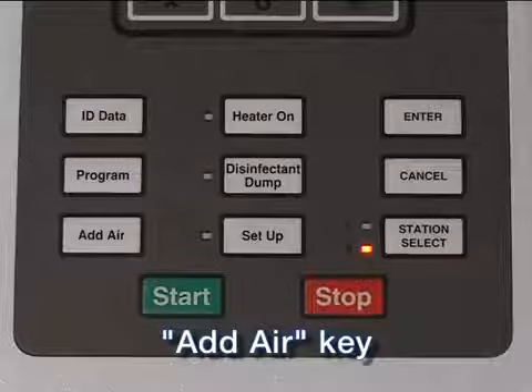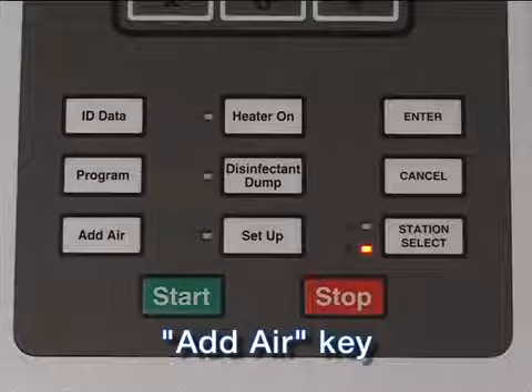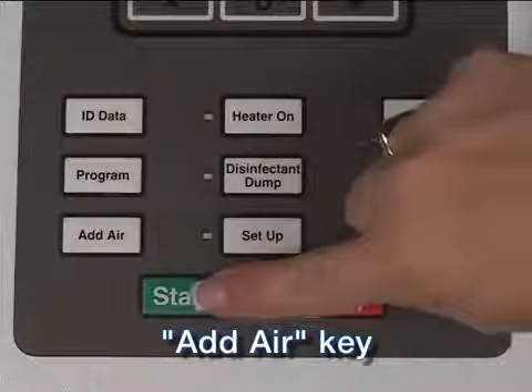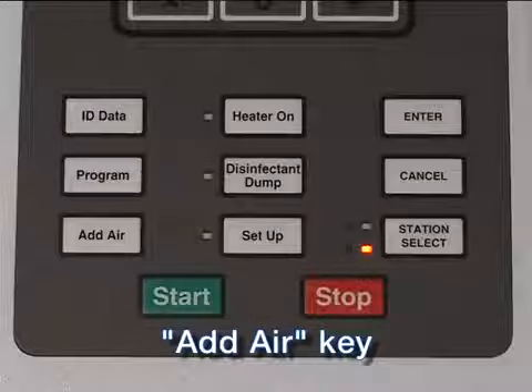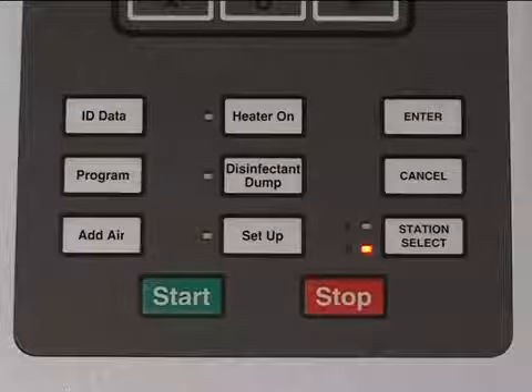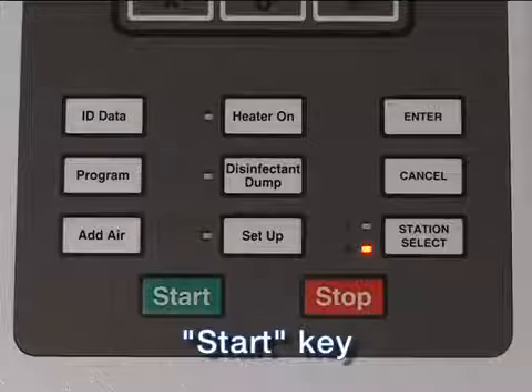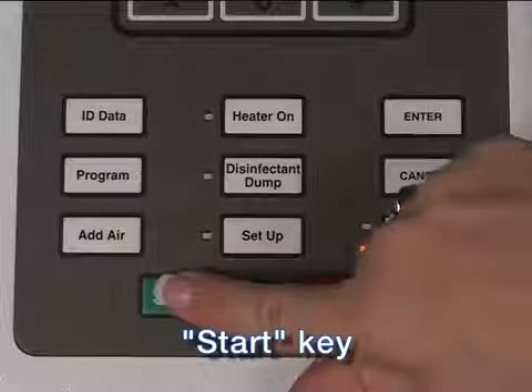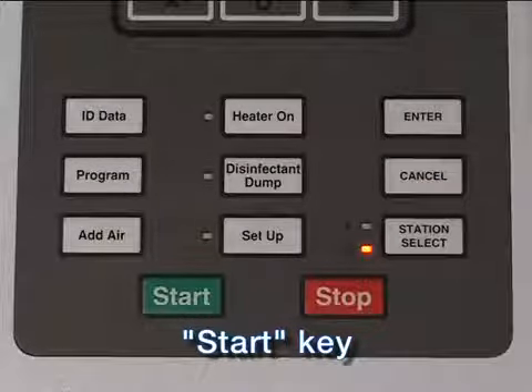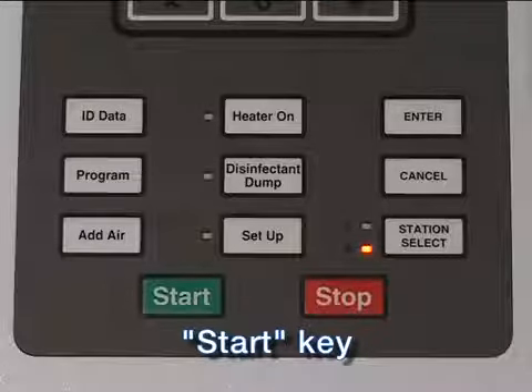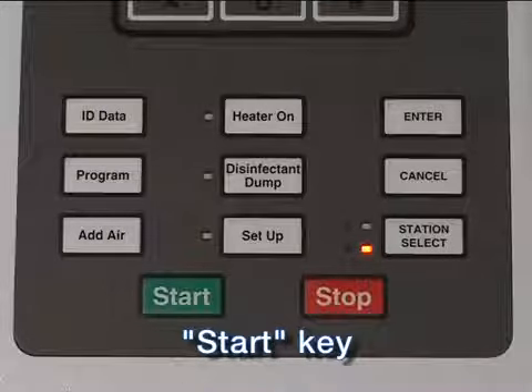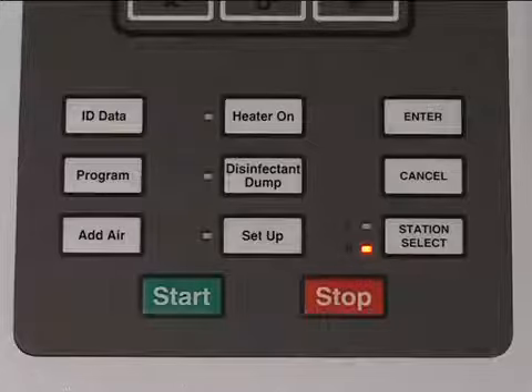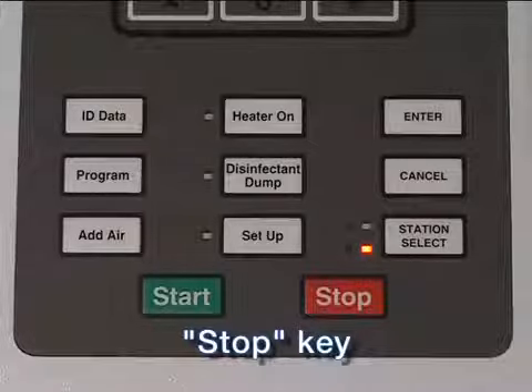Add Air key. Press this key, then the Start key to air purge the endoscope, or press during the cycle to add an extra air purge onto the end of the cycle. Start key. Pressing the Start key starts a disinfection cycle or resumes an interrupted cycle in the station selected, or starts some system functions. Stop key.